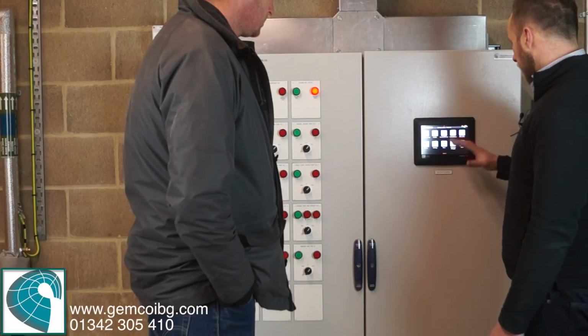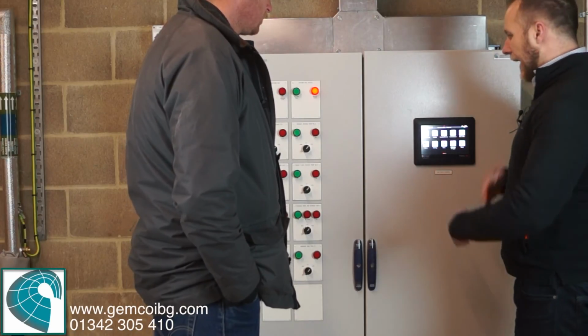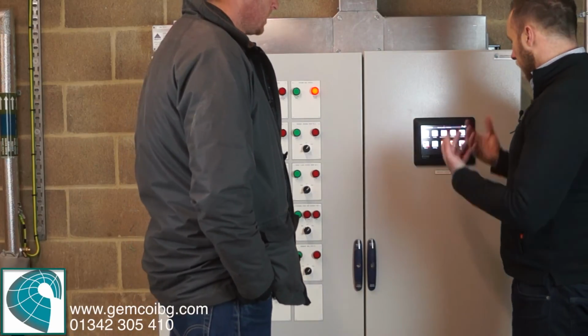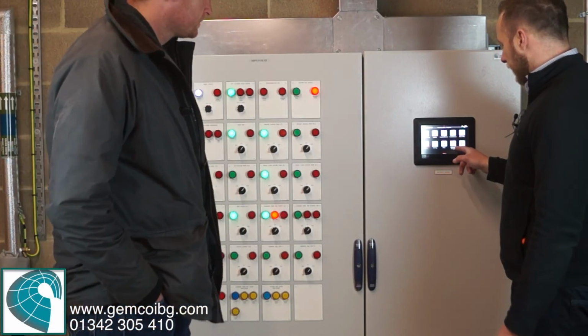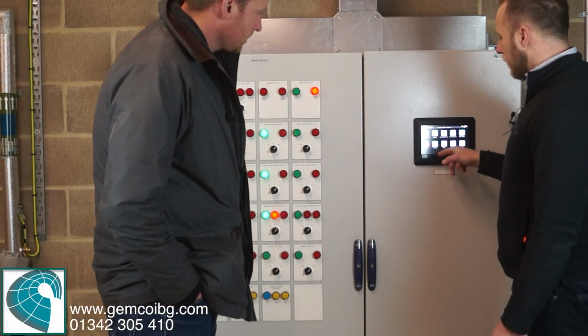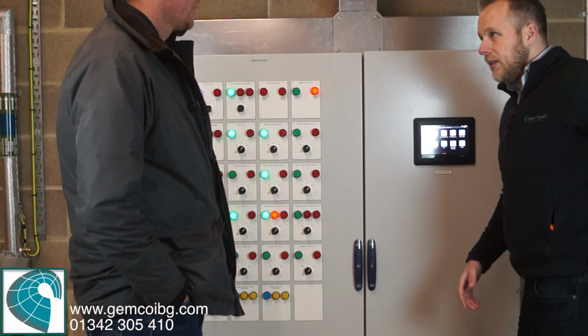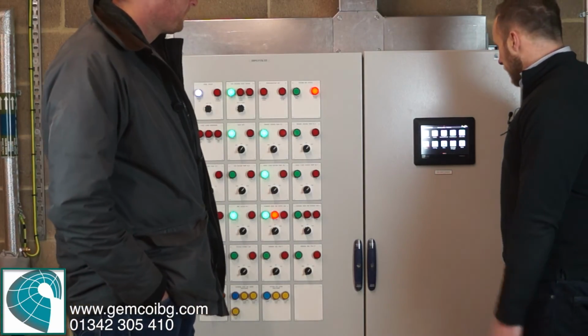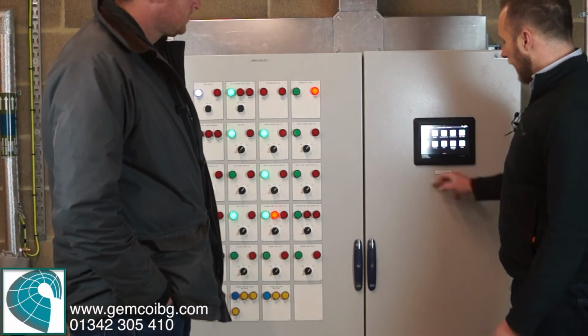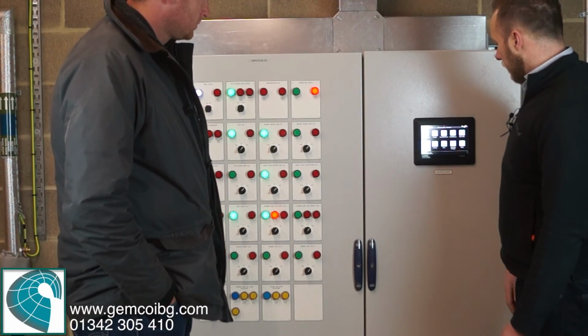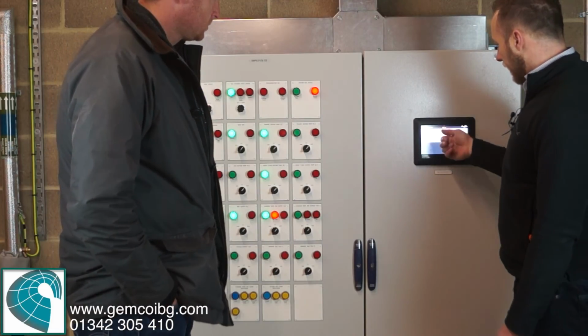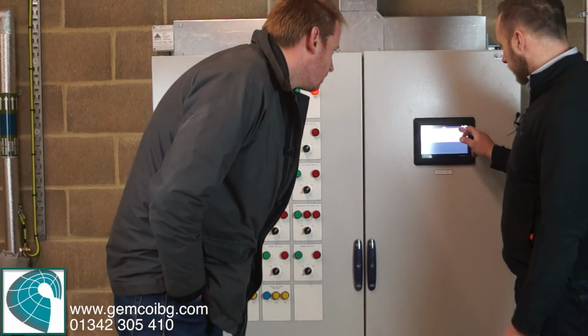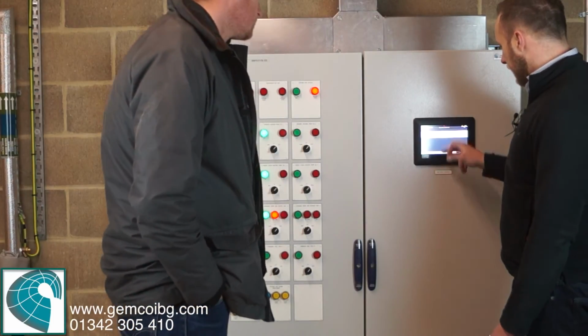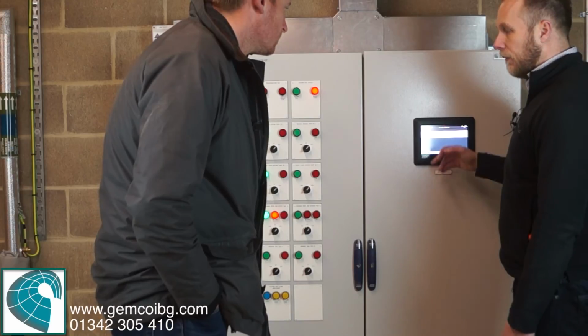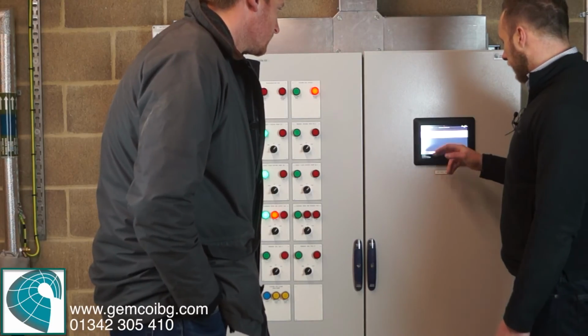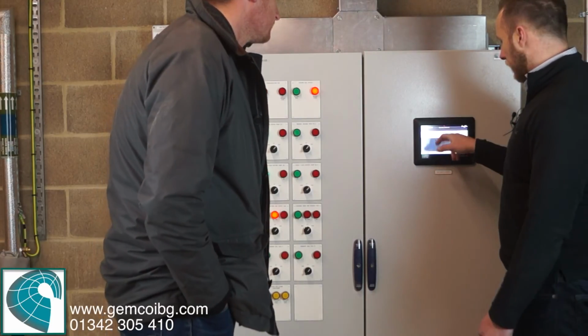Schematics, they're not loaded because you don't have any. That's if you want animated schematics to see your system working. Favorites, users, we don't set any users up because this is going to be locked, and you know who's going to be in here. Settings are to do with the actual settings of this. Alarms come up. You might have an alarm up here, and this will tell you if a pump has failed or something. So unactioned alarms: pump 2 failed, pump 1 failed. It's letting you know that pumps have failed. That's what we just did. We just forced that.